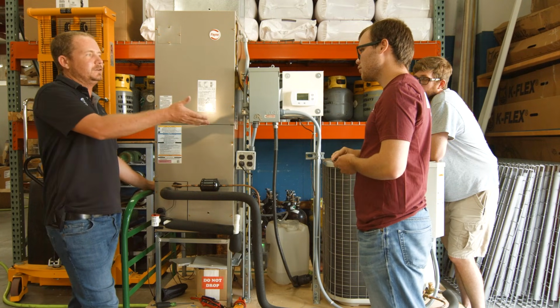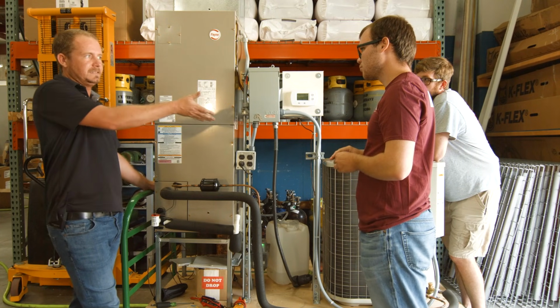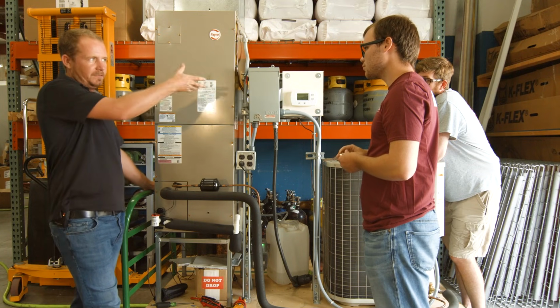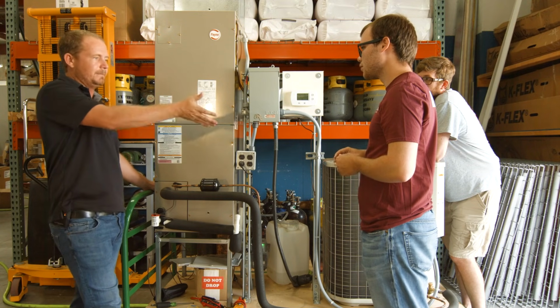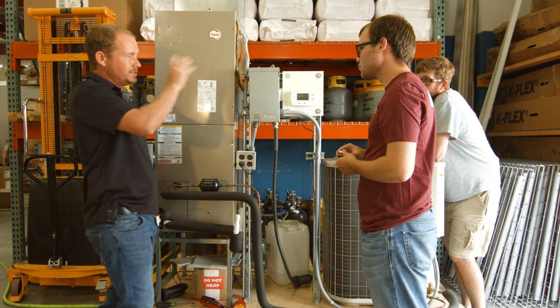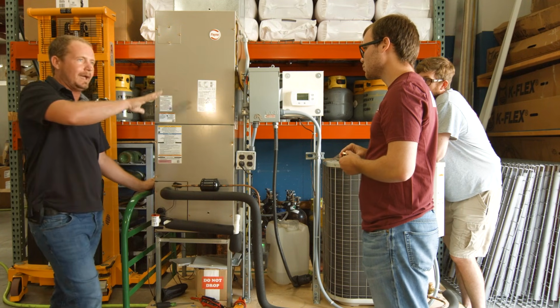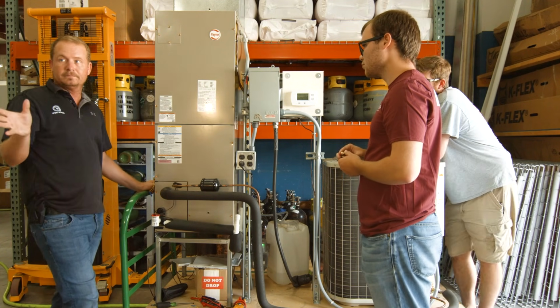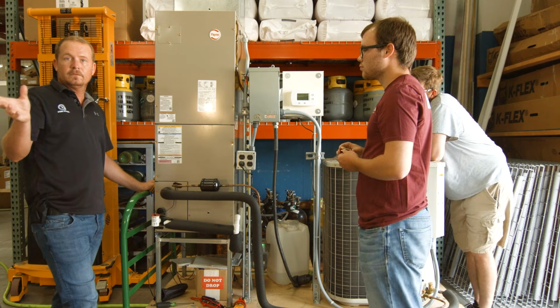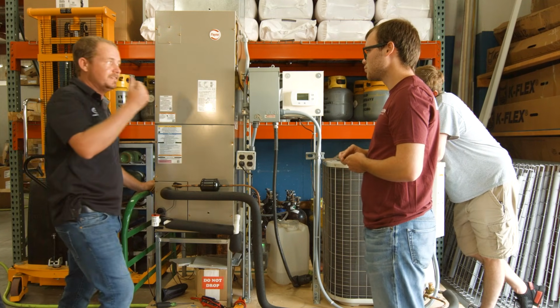All right, so you're basically using that in place of a meter. You could have pulled the face off and checked with a meter, but instead you just used that, and I'm all for it, that's a perfectly good way to do that. So what you know is that you have no 24 volt power, right? We're not feeding the thermostat.